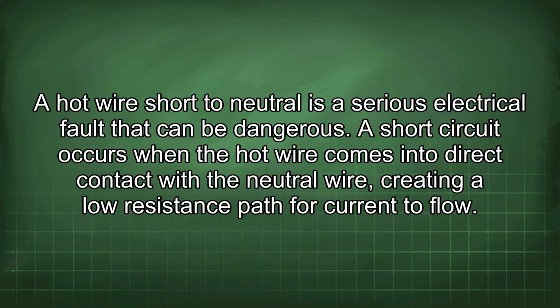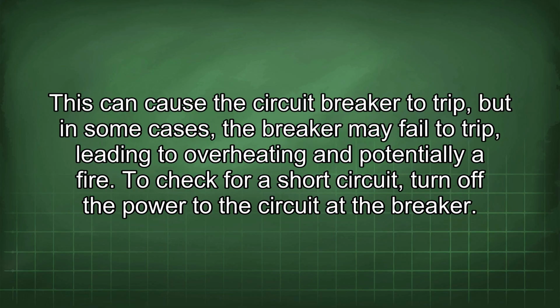A hot wire short to neutral is a serious electrical fault that can be dangerous. A short circuit occurs when the hot wire comes into direct contact with the neutral wire, creating a low resistance path for current to flow. This can cause the circuit breaker to trip, but in some cases the breaker may fail to trip, leading to overheating and potentially a fire.